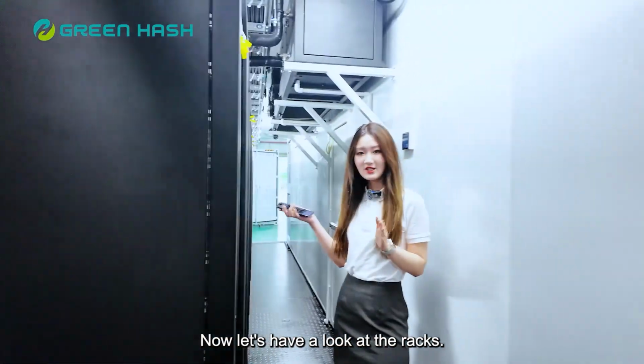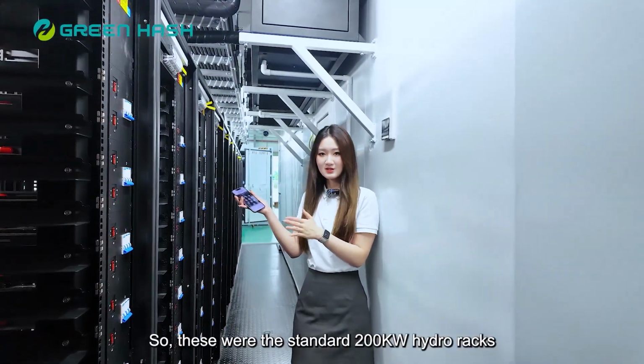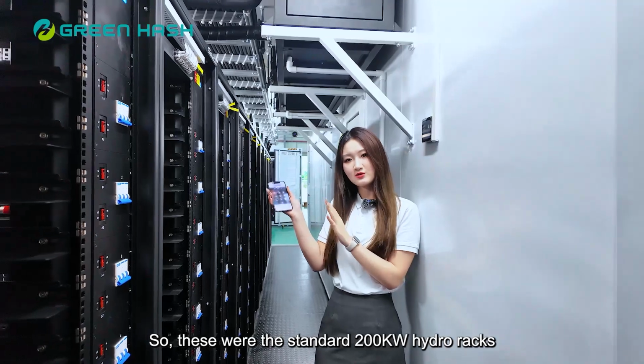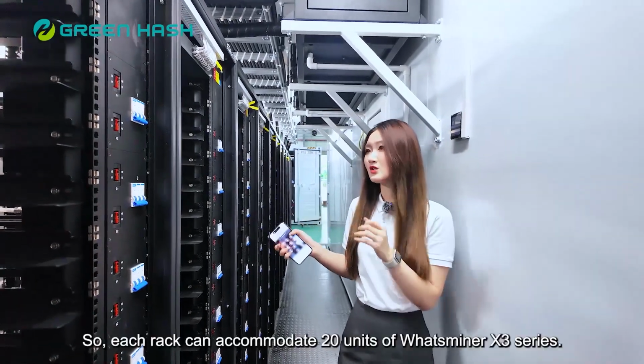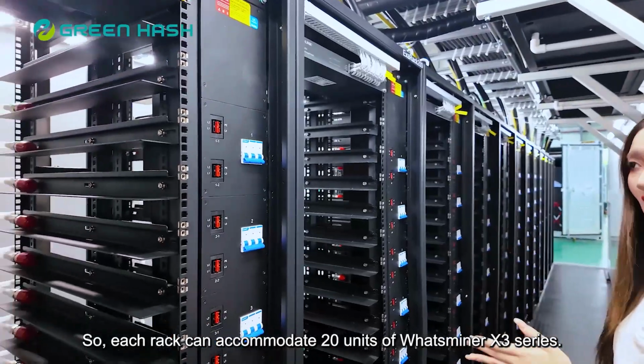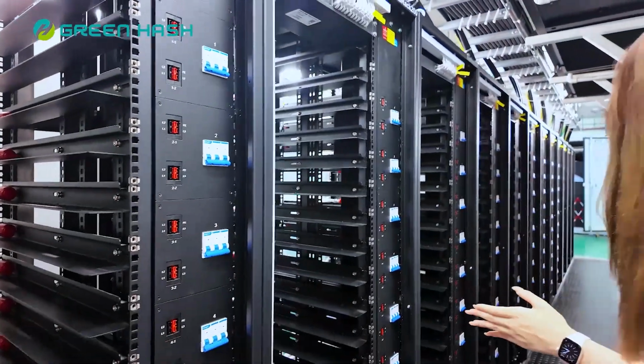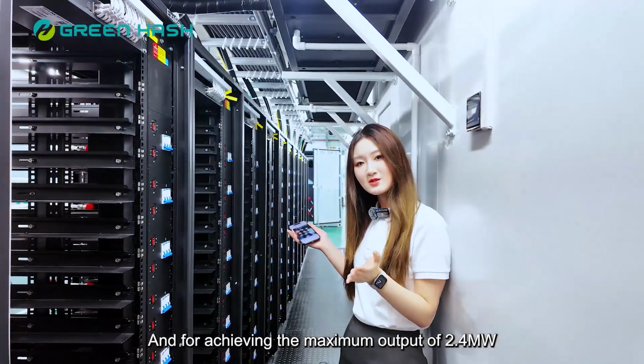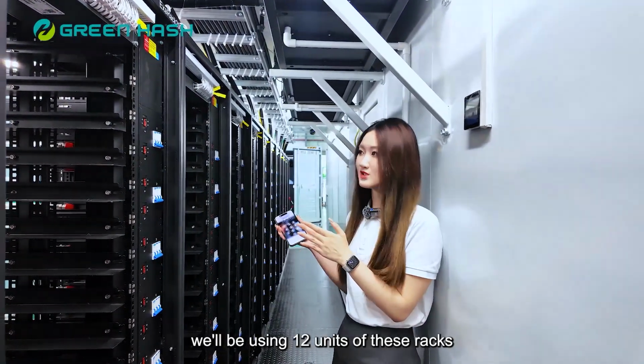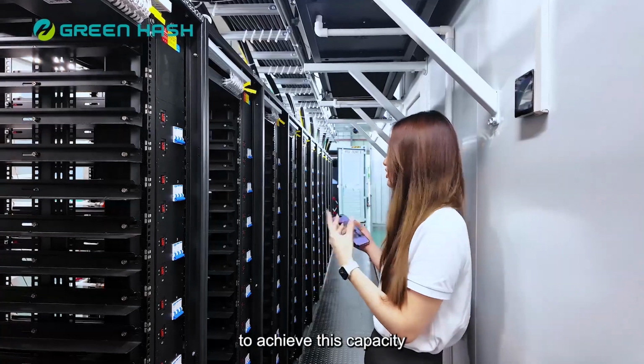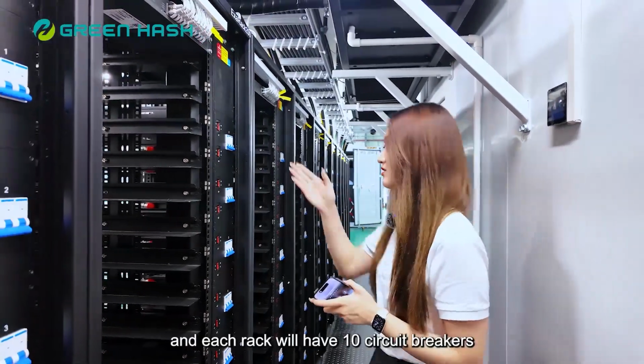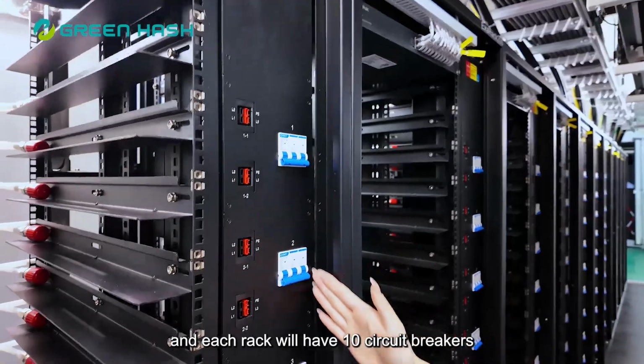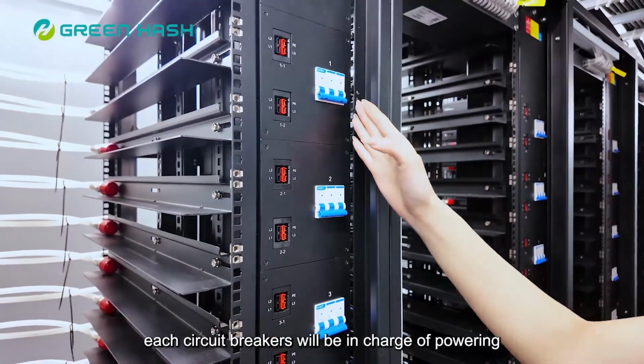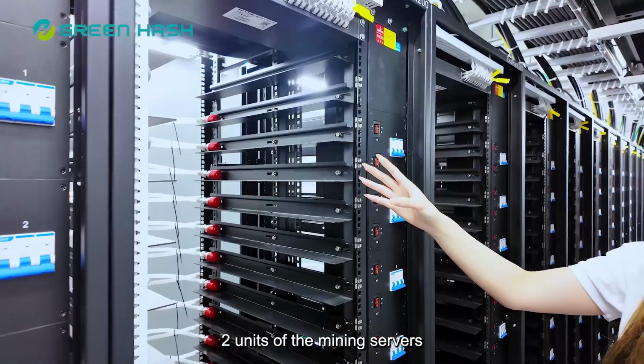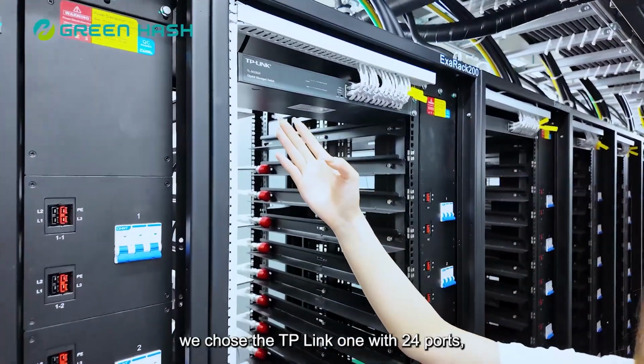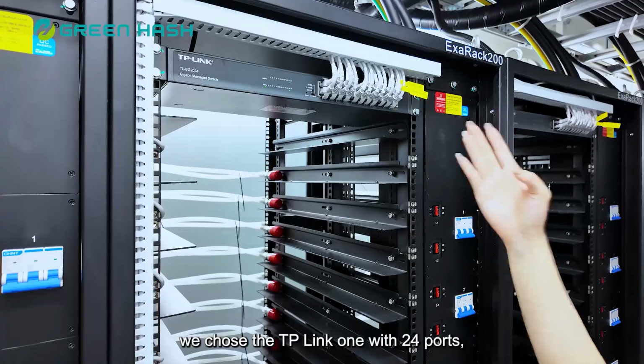Now, let's have a look at the racks. These are the standard 200 kilowatt hydro racks we designed for Whatsminer Hydro. Each rack can accommodate 20 units of Whatsminer X3 series. To achieve the maximum output of 2.4 megawatts, we'll be using 12 of these racks. Each rack will have 10 circuit breakers, and each circuit breaker is in charge of powering 2 units of the mining servers. And for the network switch, we chose the TP-Link one with 24 ports.